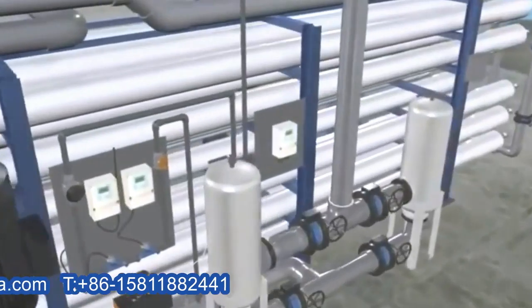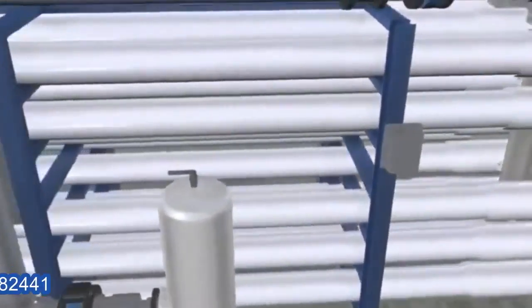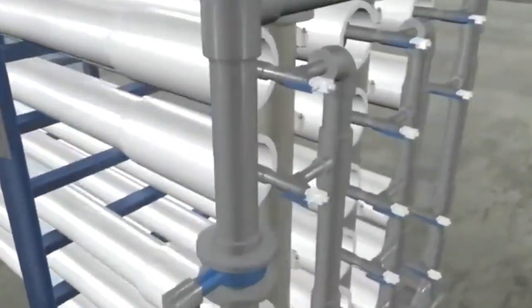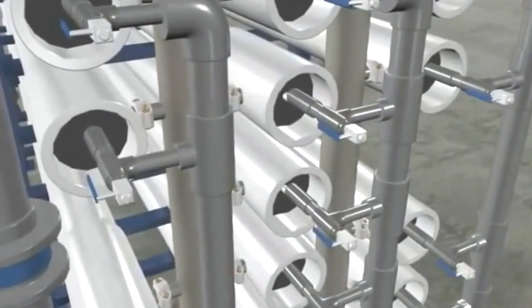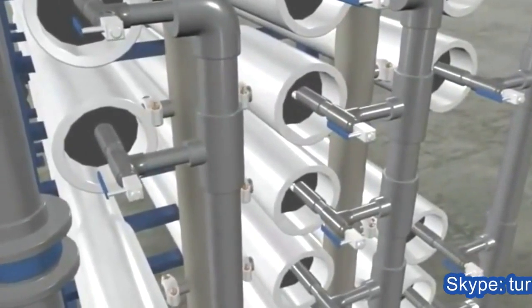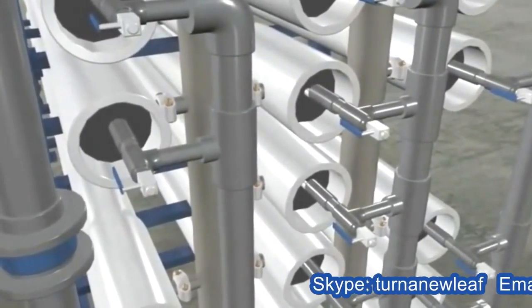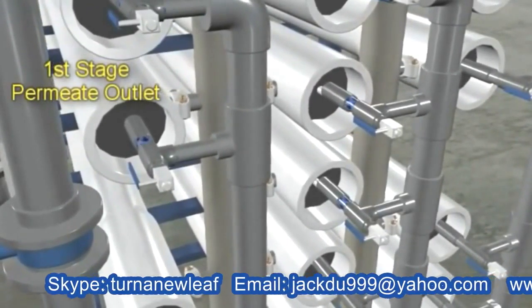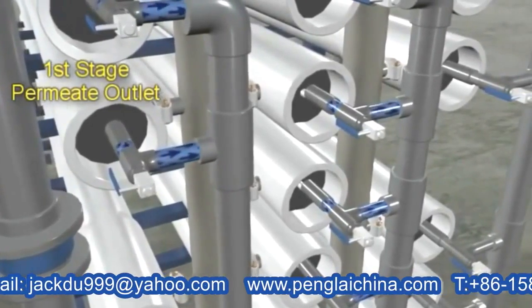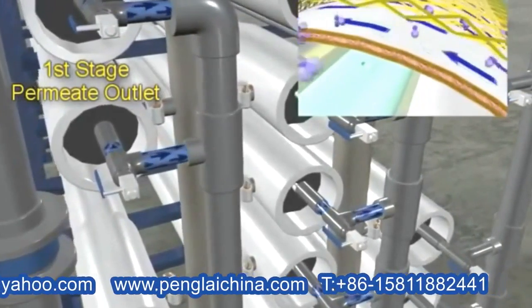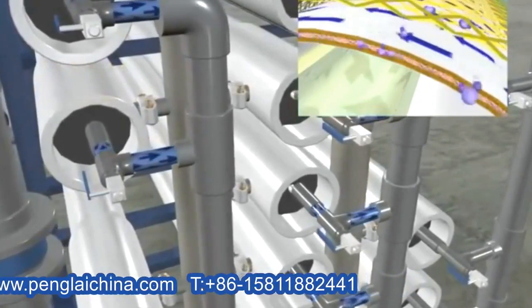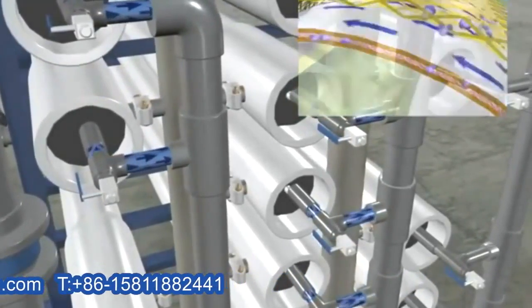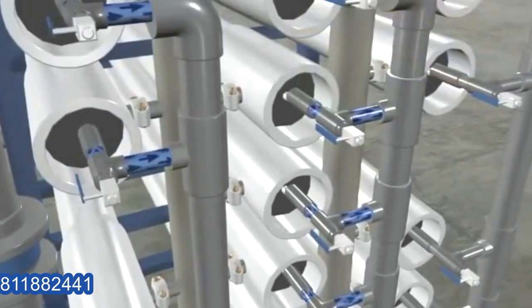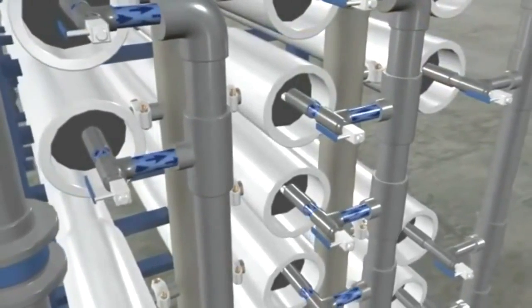As described in the RO Fundamentals section of this course, the first-stage pressure vessels have two flow paths which exit the other side of the vessel. Flow which has passed through the RO membrane is collected from a tube located in the center of the pressure vessel. This water is called permeate, due to the fact that it has permeated or passed through the membrane. It is also called product water, as it is the purified product water from the pressure vessel.